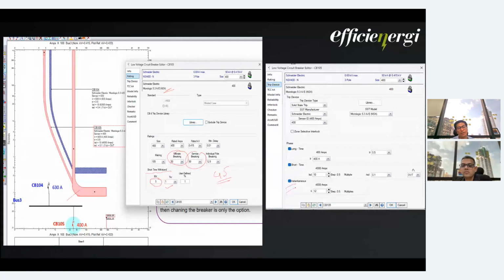But you can see the consultant, the coordination engineers will be submitting you this kind of graph, and they will be telling you that the coordination and the selectivity is done and it is proper. But this is not the case. In this instantaneous, you can see the breaker current is 4800. After 4800, the withstand capacity itself is 5 kiloampere. So after 4.8 kiloampere, it is not expected to withstand for 0.1 second or 0.4 second. It is not the capacity of the breaker.